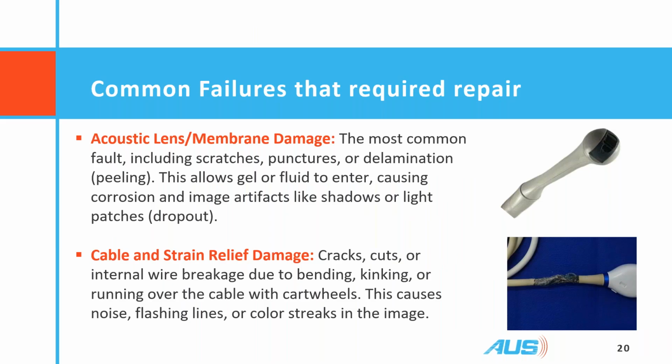So electrical safety is compromised, image quality is compromised, and it can leak fluid into the probe. So as soon as you see damage to the lens, you should take it out of service and get it repaired or replaced, which will reduce the cost of the repair because you've got it out of service before extensive damage has occurred.